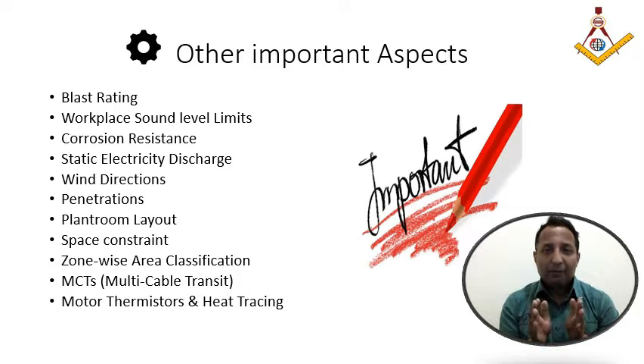So in this case, what happens? The motor which is in standby mode, the winding gets completely frozen. The winding should not freeze completely, and the motor should start properly. To keep it heated up to a certain level, the motor crankcase should be heated for the fan and AHU. A thermistor is provided for all motors above 2 kilowatt. That's the standard as per NORSOK. It keeps the motor warm. This load also we need to give to the electrical discipline so they can incorporate it in their load list, because they need to size the DG set for the requirement.